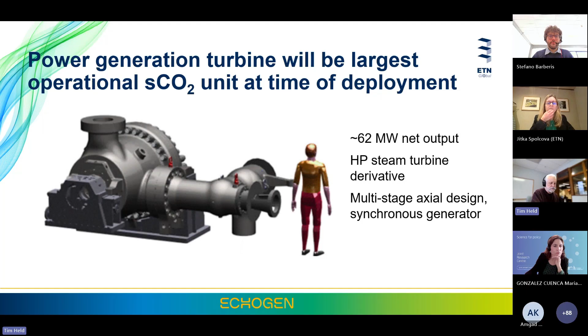Same thing on the compression side. We expect that certainly for the initial deployments, we'll be using multiple centrifugal compressors in parallel. I did want to point out, and I saw Jungseek was on the attendee list, so shout out to the University of Notre Dame and the University of Cincinnati, who are our partners in this project. We're looking at very large scale grid energy storage systems where we need more than 100 megawatts worth of compression to charge the system, and at those scales you start looking at axial compressors as a distinct possibility rather than individual centrifugals.